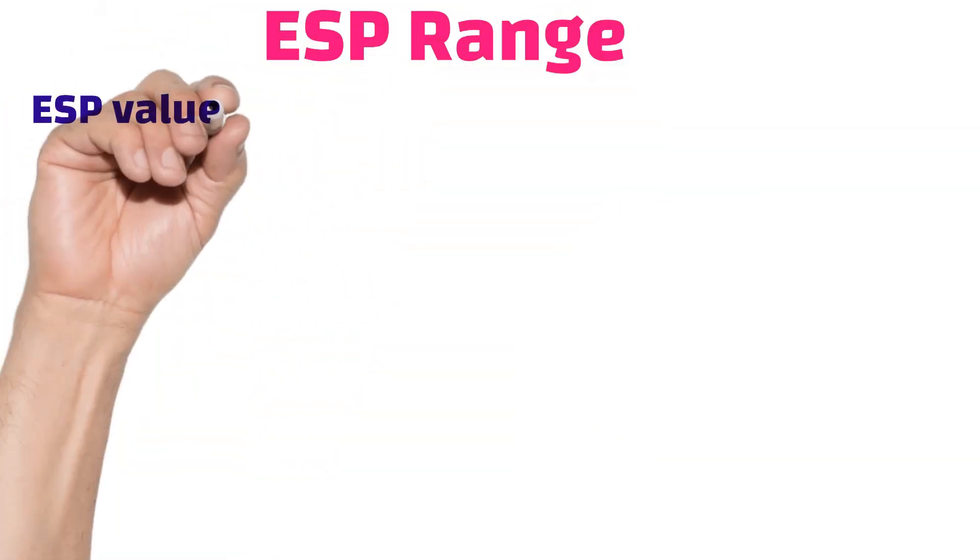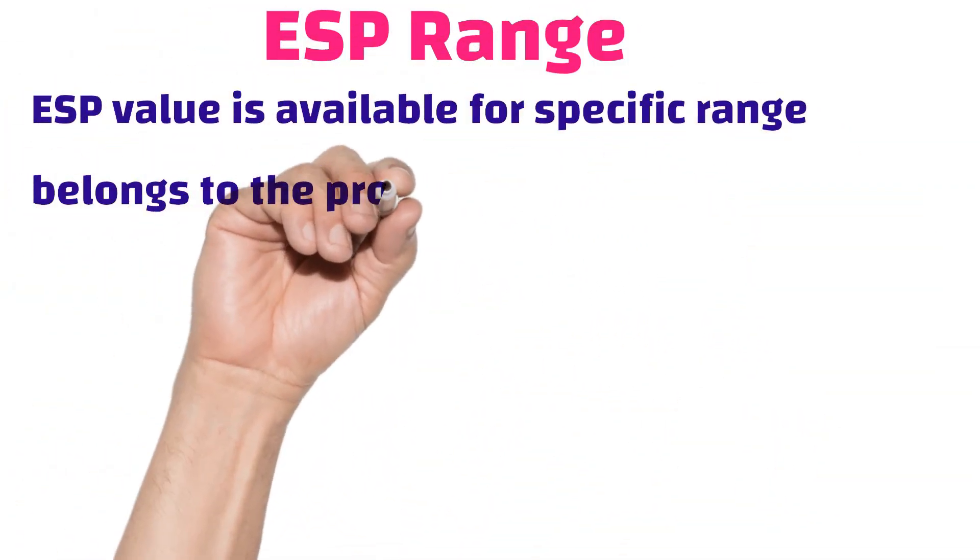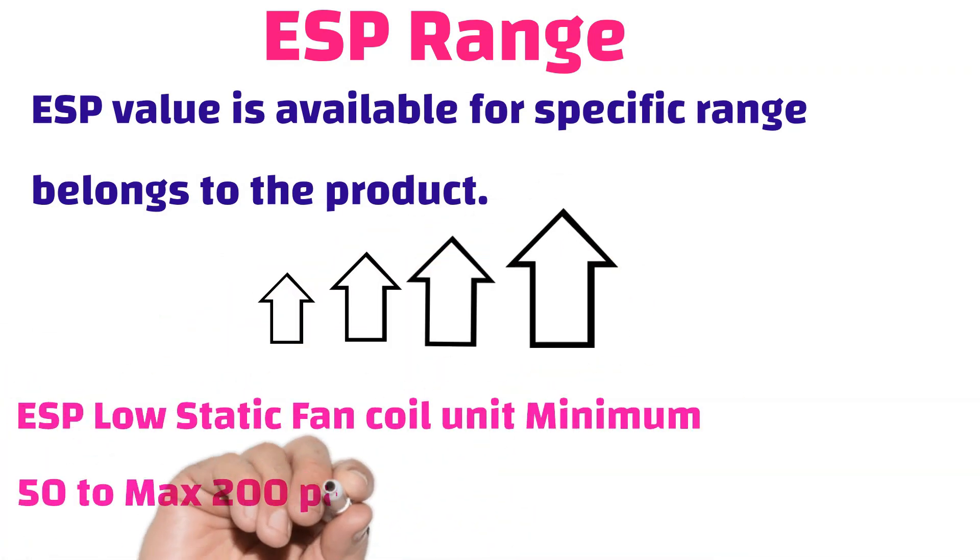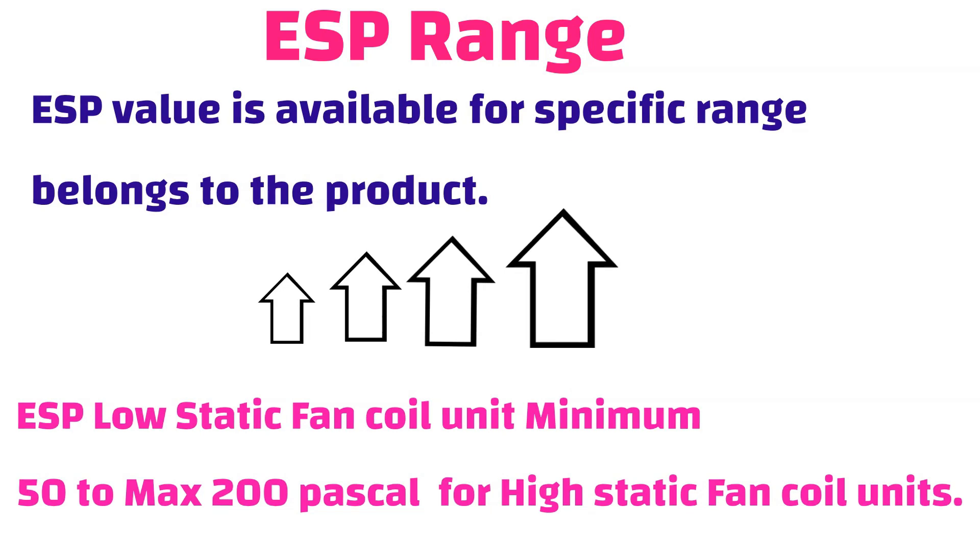Next, ESP range. ESP value is available for specific range belonging to the product. ESP of low static fan coil unit: minimum 50 Pa to maximum 200 Pa for high static fan coil units.